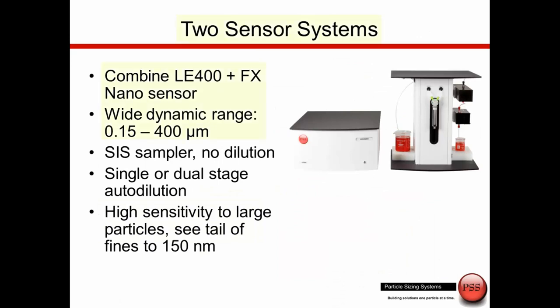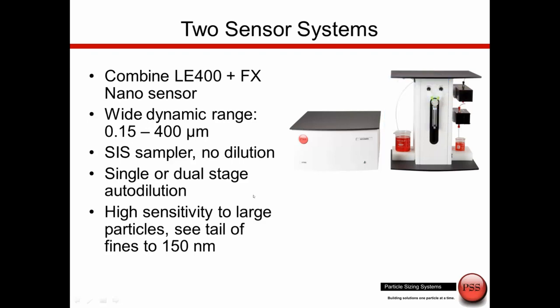If we want to combine both the FX nanosensor and the LE400 sensor, we can achieve a wider dynamic range. For certain applications such as protein aggregation, we actually use both sensors stacked together, using the SIS syringe sampler to aspirate the sample up through both sensors and perform the measurements. This allows us to see the large particles but also the tail down to very small particle sizes.